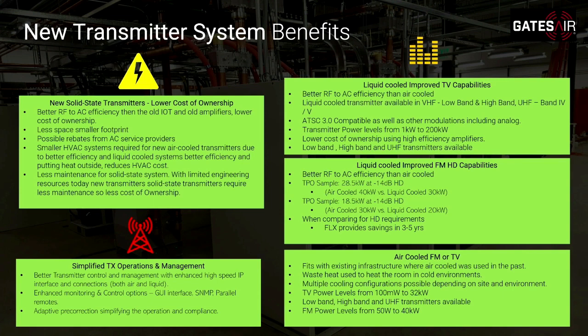Remember, we went to a solid-state device not because of efficiency, but because it's less footprint, okay? It's easier to maintain. I don't have the high voltage. I have lower voltages, and not only is it easier to maintain, but it's safer to maintain. So different parameters for liquid and air cooling. If you look at liquid cooling, and you look at FM with HD, we can do that. All these different parameters we can do.